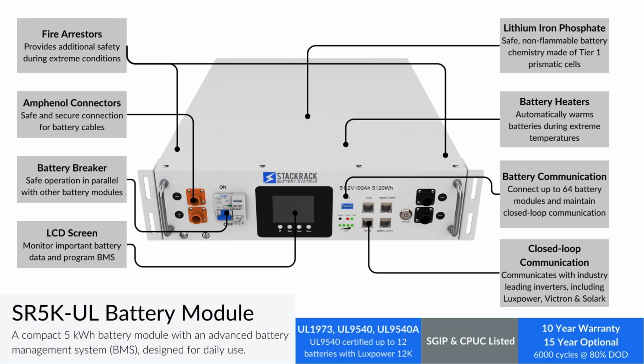So taking a look now at our SR5K UL battery module, this is a 5 kilowatt hour rack mount battery, and it has all the advanced features you're going to be looking for in a premium battery. We use tier 1 prismatic cells, lithium iron phosphate. We have integrated fire arresters, pre-charge resistors. There's Amphenol connectors for easy connection of battery cables. The BMS allows up to 64 battery modules to communicate together for a total of 320 kilowatt hours.